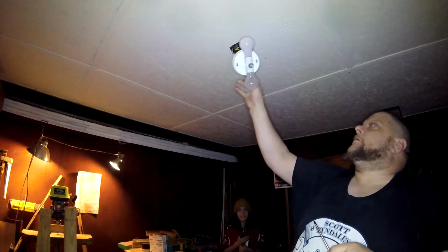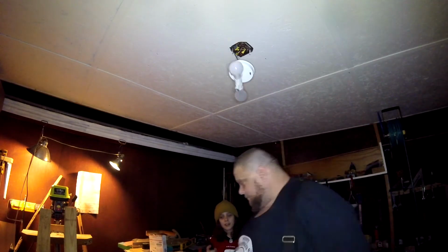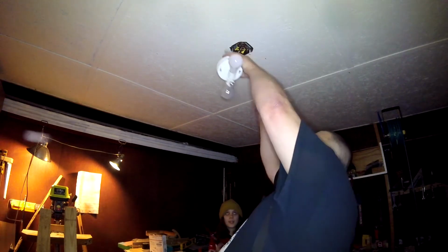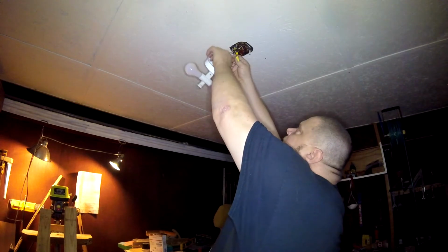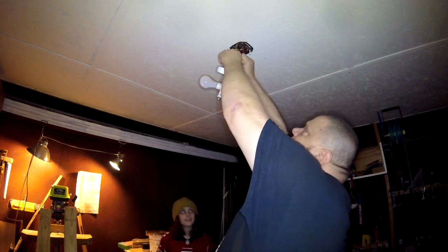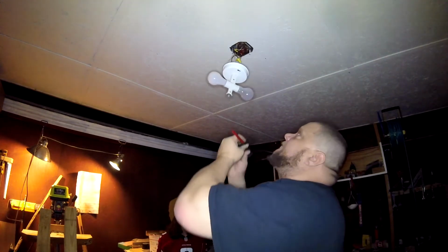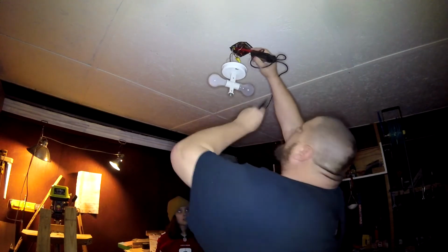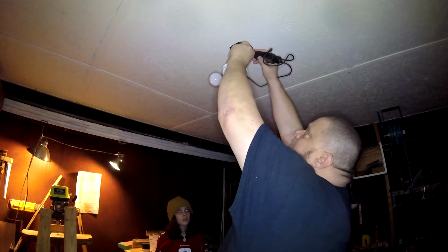I don't plan to. Believe it or not, this is actually a fan-rated box. Here's your wiggy. So we're going to pull this down. And in the back, let me see it. So what you have to do, I've already tested the meter on a known live circuit. So we're going to push this one down in the back of that one. Check the box. Here, go turn the light on. Alright, turn it off. On.